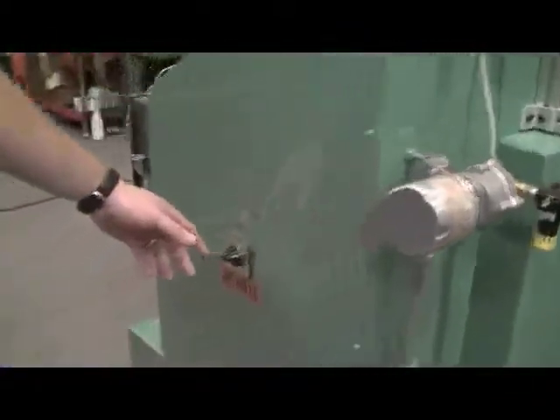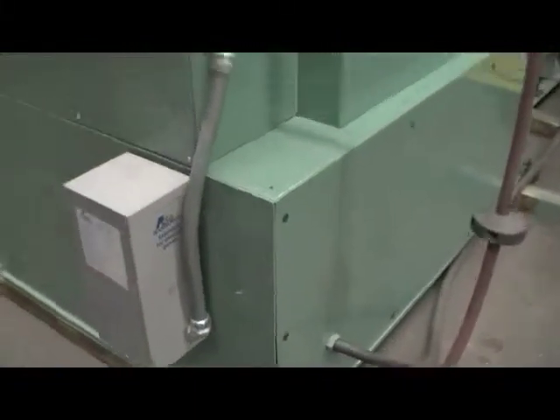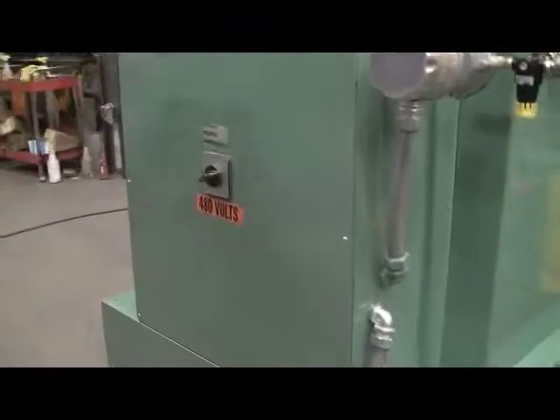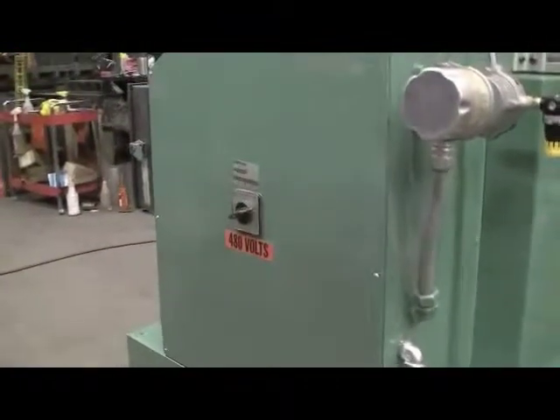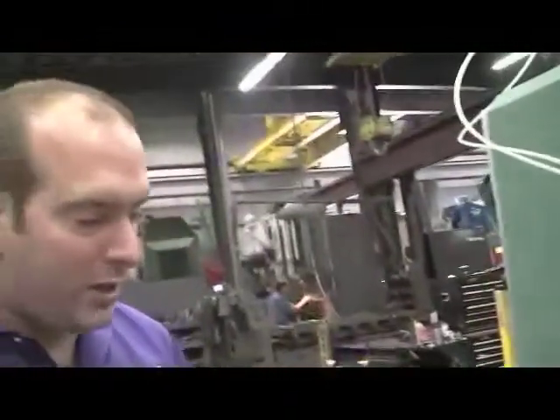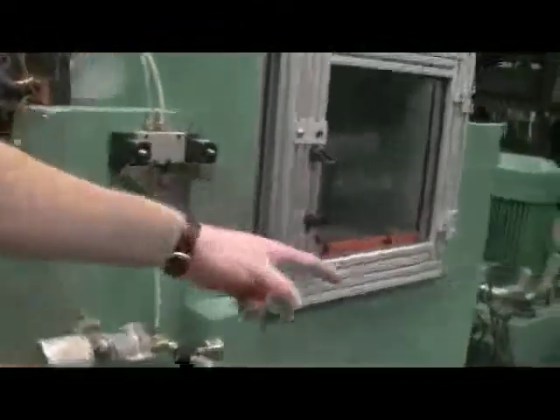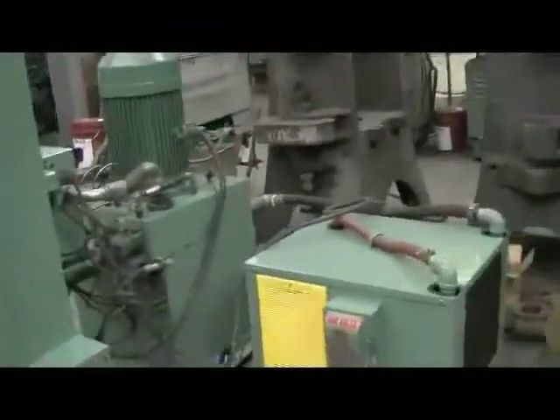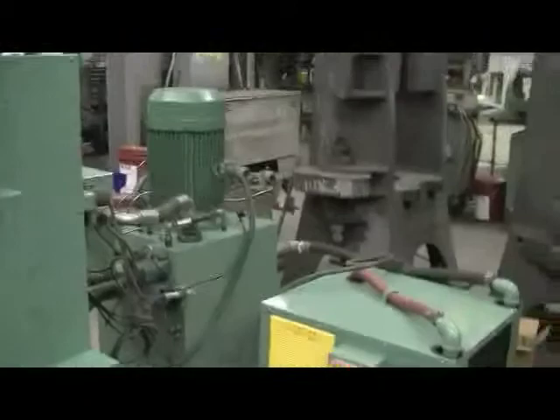And over here is your main disconnect and the main wires that feed the panel. It's currently wired for 480 volts. We did have the motor rewound, so it'll accept 230 or 460, but you would have to do some wiring to change that over. Although there's three motors, you got the main motor, and then you have two motors in the chiller that would all have to be changed over, and then also the transformers inside of the control box.